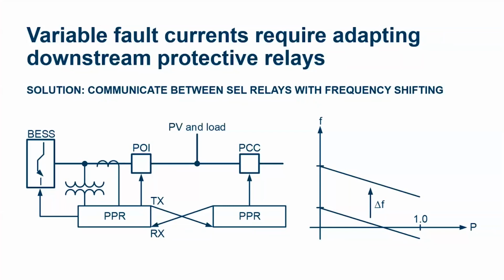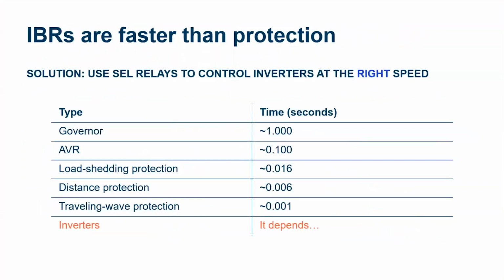You have the programmable protective SEL relay, the PPR, tell the battery inverter, please shift your frequency. Inverters are great at shifting frequency. They can shift all day long. They don't care. Shift the frequency with the speed of light. Those relays 20 kilometers away now know they're islanded and can switch to a more sensitive protection algorithm, solving a complex problem with the relays that you already own. Inverter-based resources can be faster than the very protective relays you apply to your grid to protect your customers and protect those inverters. And so we like to put protective relays to control the inverter-based resources so that we control them at the right speed.